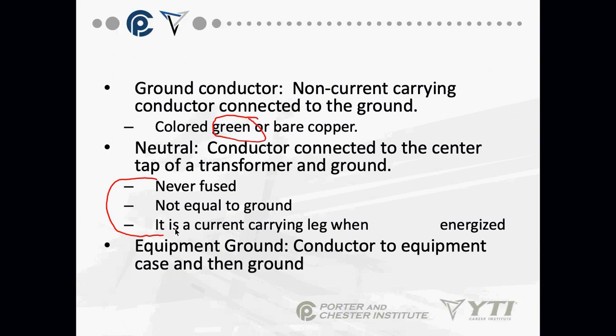The reason I stress this so heavily is that in a commercial building, especially in our shops, neutral can be energized. You've got to be very careful. When you're working in the shop, do you always trust the person working next to you? No. How about the electricians working in the next shop? Do you trust them? Nope, trust nobody. That's my point - always check on your own. It's important, you can get really badly zapped by neutral if it's not connected properly. People wire things wrong a lot, especially when you're learning.